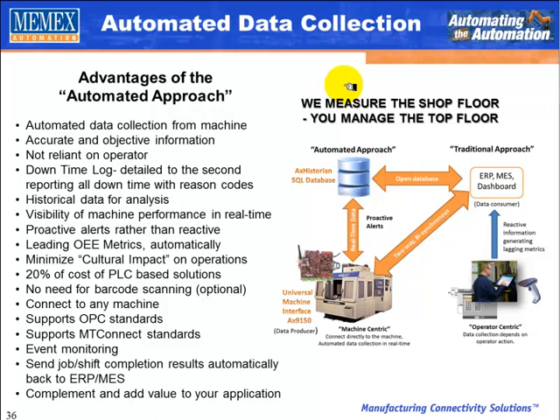For example, if a machine is down for longer than 10 minutes, the system can alert the maintenance people to go to that particular area — so you don't have to rely on the operator to do these sorts of things. There's no need for barcode scanning when you're collecting information directly from the machine, and the solution supports OPC standards and MTConnect standards with event monitoring, truly complementing and adding value to your overall business applications.